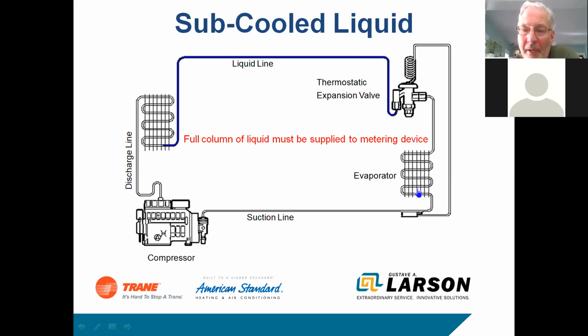So it's the basic refrigeration cycle, and all the valve is doing is reacting to this temperature right here, and it's opening and closing to keep the proper amount of refrigerant in the coil. Again, it could be 20 degrees of superheat, could be 22, 23 if it's got a really high return. A new system you just put in on a 90-degree day may be very high until it gets to the house. But don't condemn the valve till we've looked at all the other things.